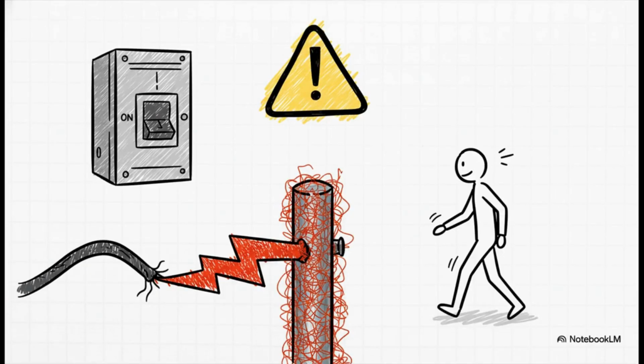So you see, it doesn't matter what system type you have. The ultimate danger, the real nightmare scenario, is a fault that energizes a piece of metal that isn't bonded. The path for the current is often so weak that it won't trip any protection. That means that piece of metal could stay live at a lethal voltage indefinitely, just waiting.